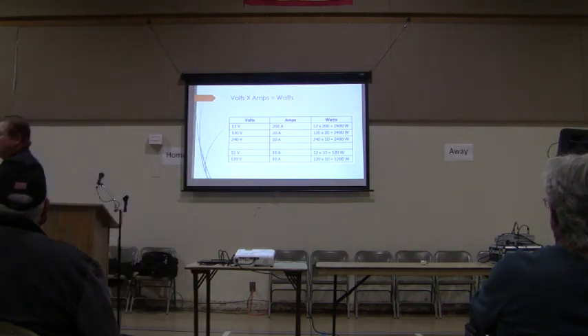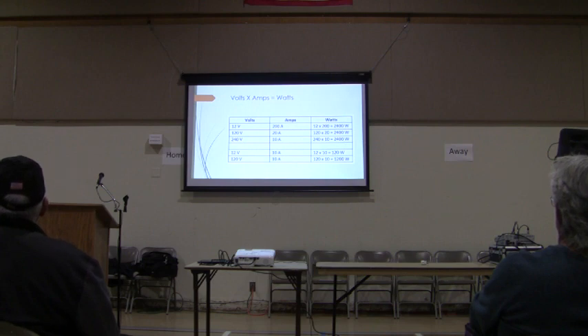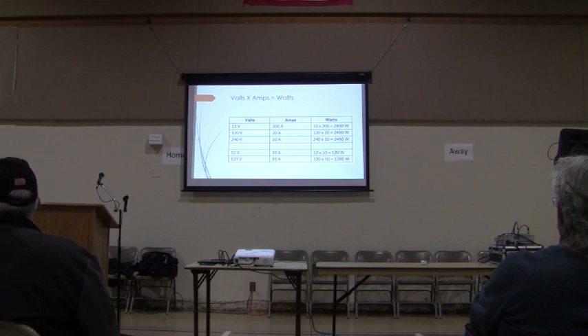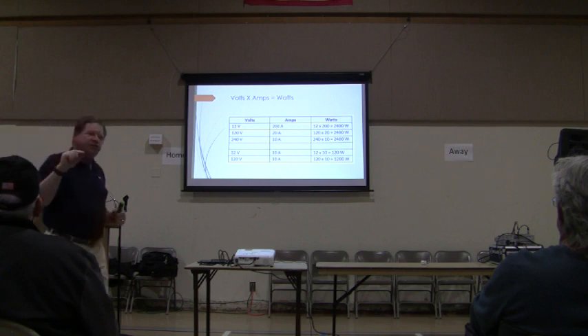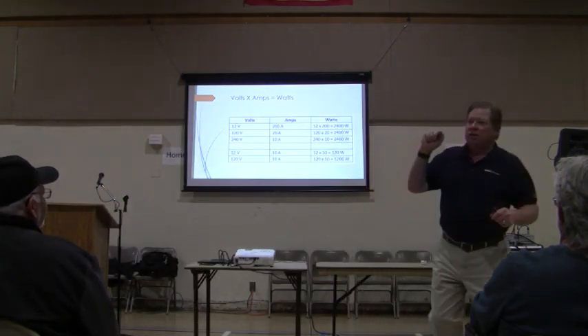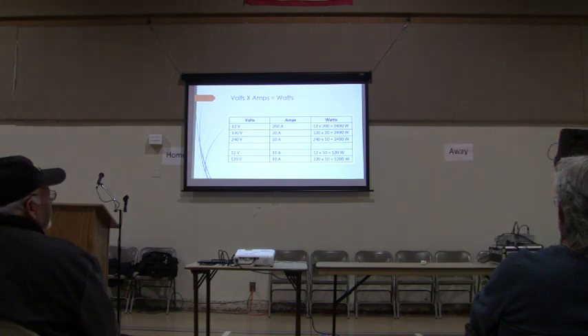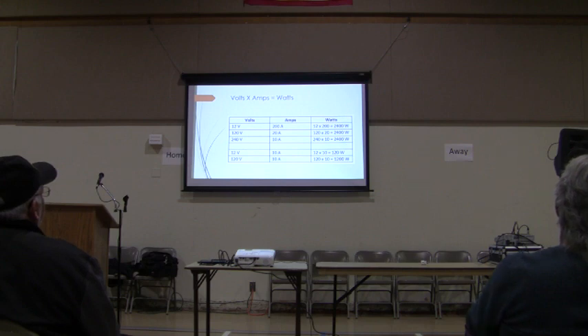So the way this works - if you bought a small 2,000 watt portable and your refrigerator takes 2,500 in surge, is that a no-go? It may well be. You'll pop a circuit breaker, you'll be able to reset it - you won't damage the generator, you won't help the refrigerator. So if I know it takes 2,500, I should look at that. That brings up something I didn't mention with inverters: when you look at the model number, it's often the surge or inrush watts, not the running capacity. Like that Honda 2200 I showed you - that was the surge wattage, not the running watts, which were either 1,600 or 1,800.